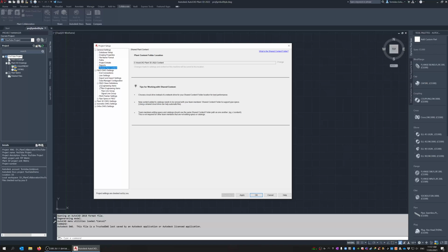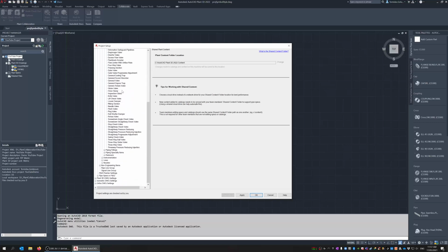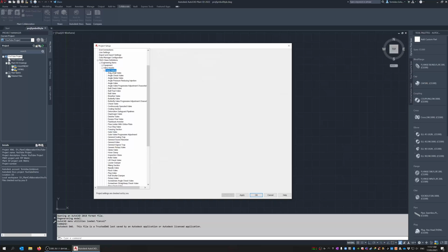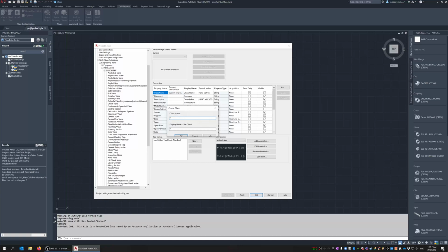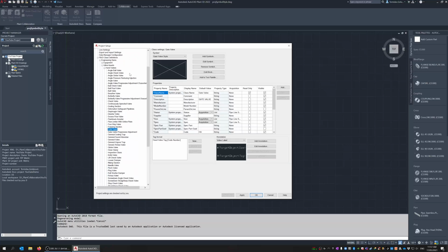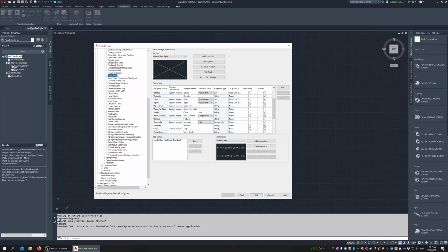And one of the other things as well is these inline assets. So things like valves, this doesn't have to necessarily be valves, but valves is just a good example. I don't usually like to play with the standard valve symbology. I like to leave it, and then I make a new one here, and I'll call it Tech Nexus Gate Valve. Okay, and then under here, I can have my own client-specific or company-specific gate valves, and then I'd add symbols from up here. The only reason I like to do that is just from a checking standpoint. If I know the standard gate valve works and mine doesn't, then at least I can troubleshoot what I've done or go back and see what the standard one is doing in regards to any other properties, and then I can go back and apply them to here as well.